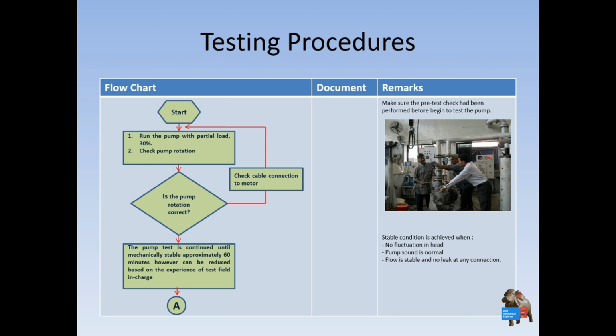It's a very simple procedure. Let's see from this flow chart. After the pre-test you have done, we go to the testing procedure. Let's say, for example, you are ready to test. You install the pump, piping, everything, etc. There is no more leaking in the piping system, and the water is enough. Then you open the valve, let's say 30%, and run the pump to make it warm. Let's say you wait 5 to 10 minutes to ensure it is warm.